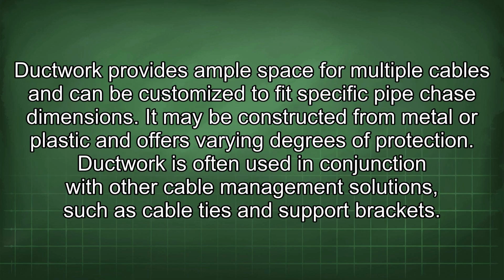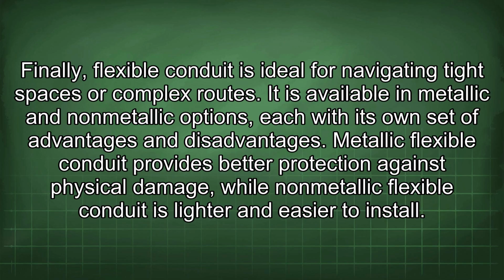Ductwork provides ample space for multiple cables and can be customized to fit specific pipe chase dimensions. It may be constructed from metal or plastic and offers varying degrees of protection. Ductwork is often used in conjunction with other cable management solutions such as cable ties and support brackets. Finally, flexible conduit is ideal for navigating tight spaces or complex routes. It is available in metallic and non-metallic options, each with its own set of advantages and disadvantages. Metallic flexible conduit provides better protection against physical damage, while non-metallic flexible conduit is lighter and easier to install.